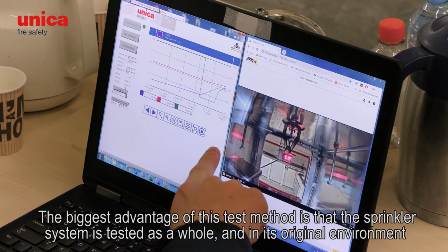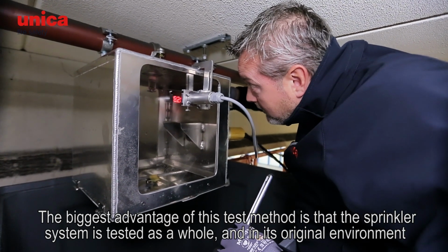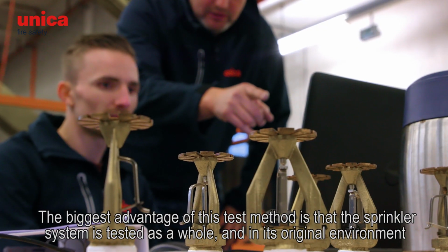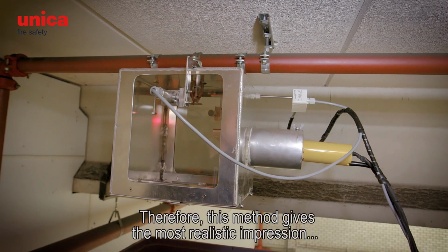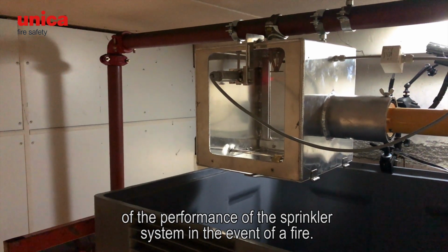The biggest advantage of this test method is that the sprinkler system is tested as a whole and in its original environment. Therefore, this method gives the most realistic impression of the performance of the sprinkler system in the event of a fire.